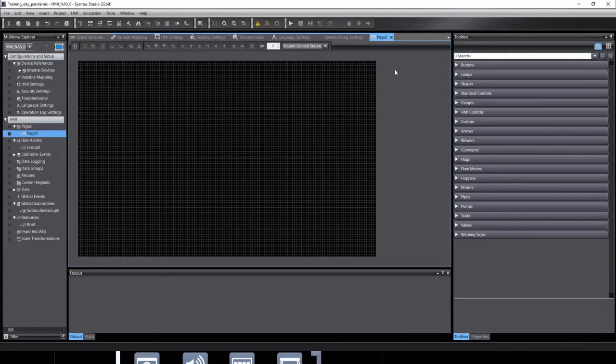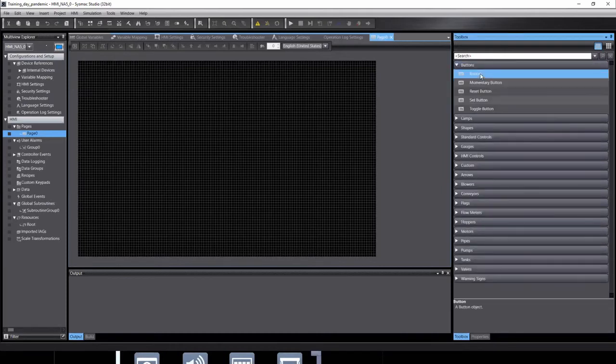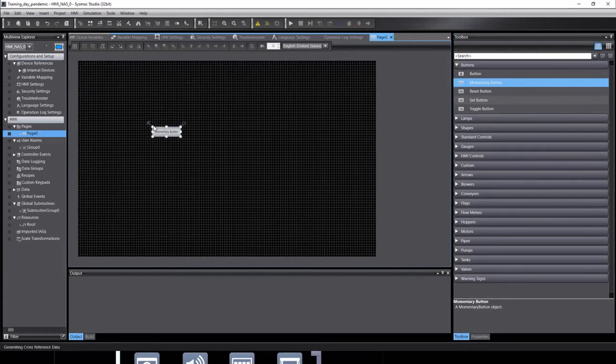If you guys remember, in the PLC programming environment, we had one contact and we had one coil, and depending on what you selected it to do would determine its function. So you'd right click on a contact and you could choose normally open, normally closed, one shot up, one shot down. On our HMIs, we have one button. Well, a few technically. Button and momentary button just determines whether it's toggled or whether it's a momentary.